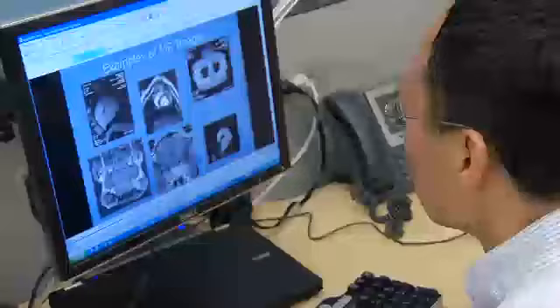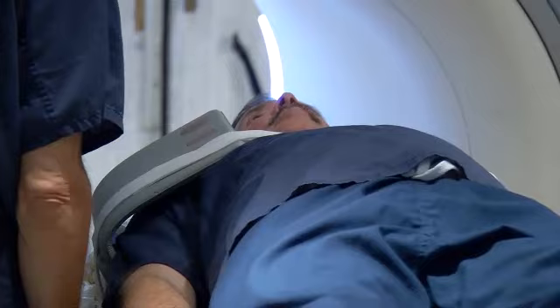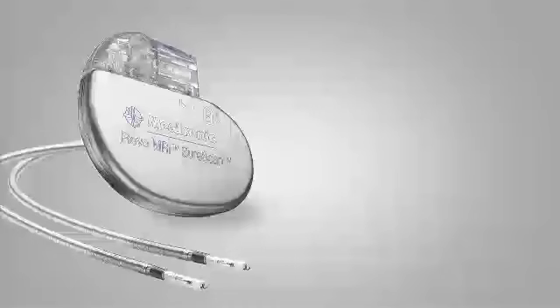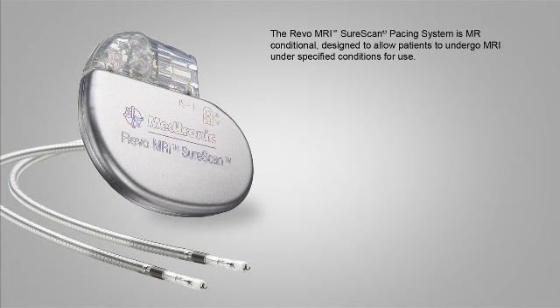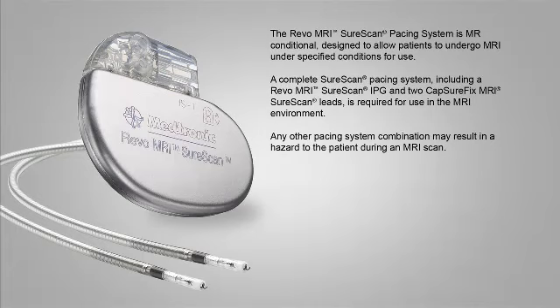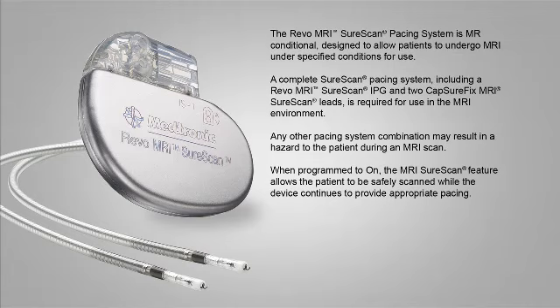As we come into the market in the U.S., we bring a system that's been thoroughly analyzed, designed, tested, and clinically proven to be safe in the MRI environment — ahead of anyone else in the industry. The REVO MRI SureScan Pacing System is MR conditional, designed to allow patients to undergo MRI under specified conditions for use. A complete SureScan Pacing System, including a REVO MRI SureScan IPG and two CapSureFix MRI SureScan leads, is required for use in the MRI environment. Any other pacing system combination may result in a hazard to the patient during an MRI scan. When programmed to on, the MRI SureScan feature allows the patient to be safely scanned while the device continues to provide appropriate pacing.